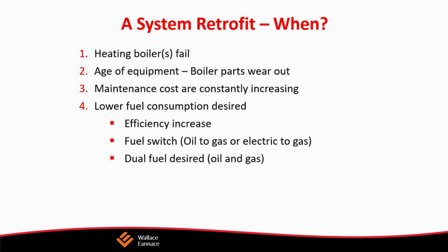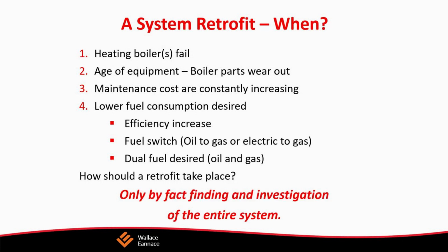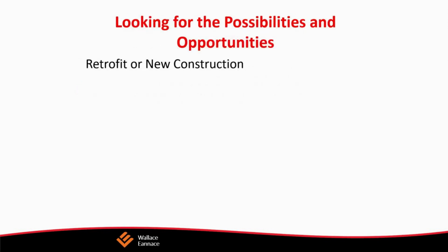So if you have a boiler like that, why did it fail? Well, it could simply be too old. Parts wore out, and it became unreasonable to keep this thing running. This boiler is constantly getting water flowing through it, and it also is getting hot and cold, so you have thermal stresses and mechanical stresses. On the fire side, corrosion can build up. You can have flue gas condensation. When that flue gas condenses, it leaves acids, and those acids eat right through the metal.